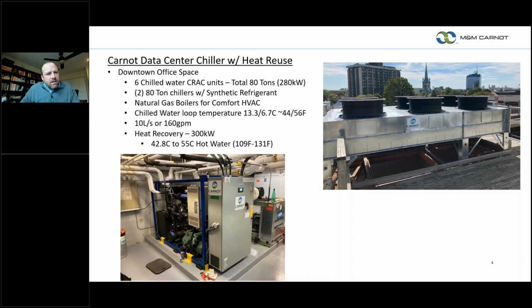So just a couple of the specifics. It was a 44 to 56 chilled water loop, I think in Fahrenheit, but I put the Celsius there as well. So 13.3 and 6.7. I think I reversed that, but those are the temperatures that the data center needed to cool the equipment, at around 160 GPM. But what we were able to do with the refrigeration system was to basically generate 300 kW of usable heat that would go into the building.